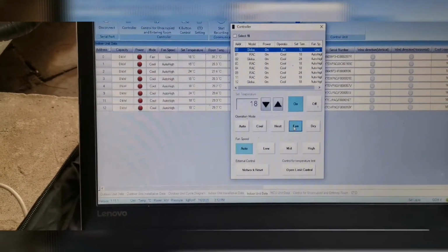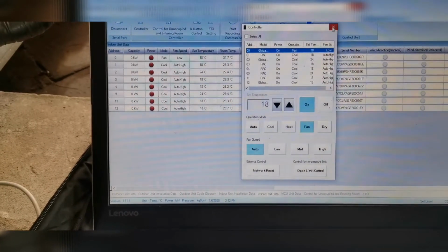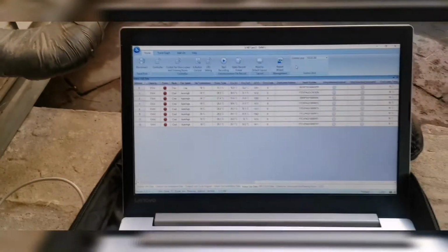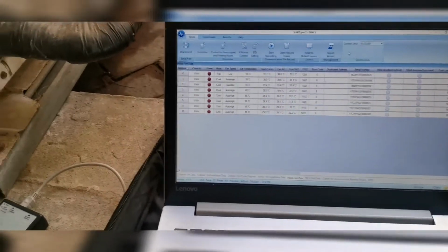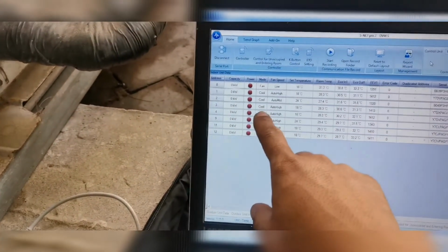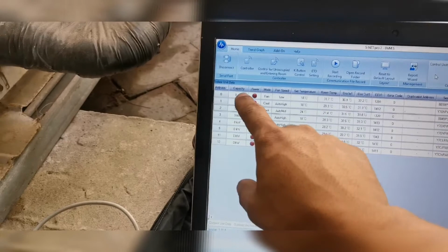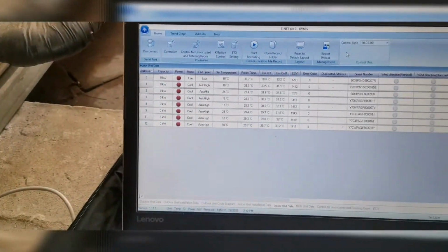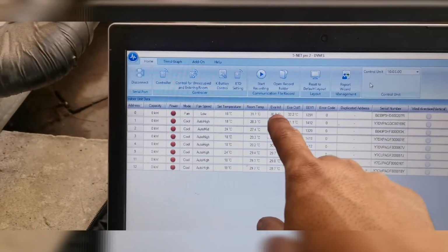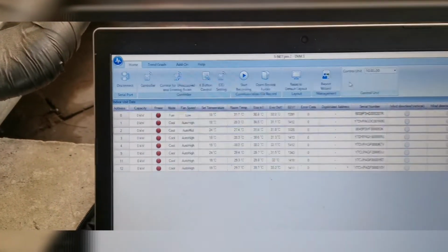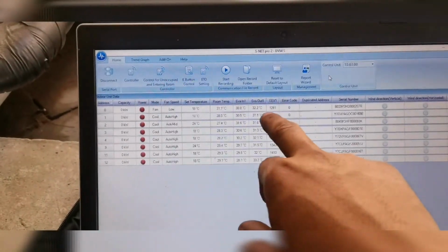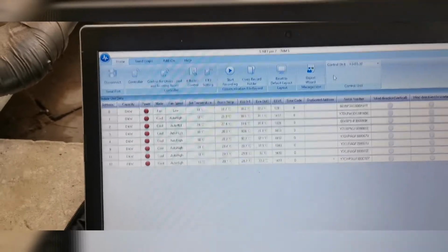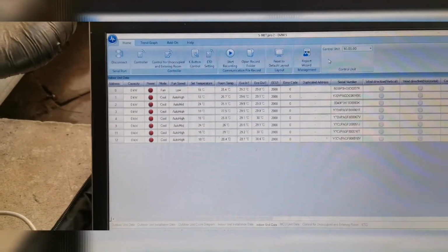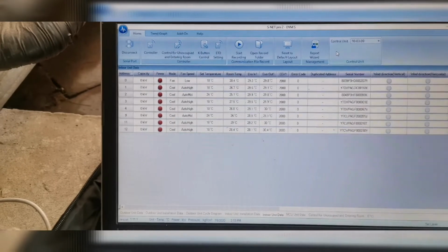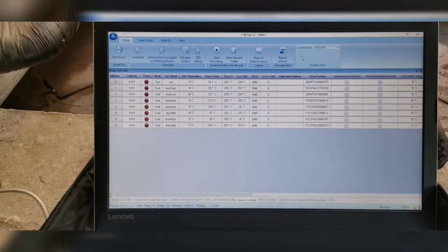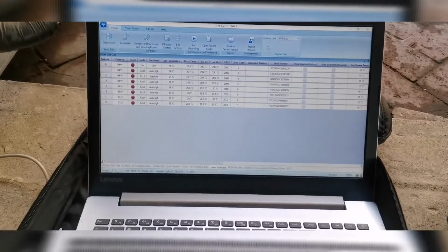Alright, so I'll close that, and as you can see, the rest of the systems are all on cool. The top one is on fan only, and we're going to verify that this EVA in and EVA out sensors are not causing our EEV, electronic expansion valve, to open in cooling mode. So in heating mode it works perfectly fine, but in cooling mode we seem to be having some issues, so we are going to verify that.